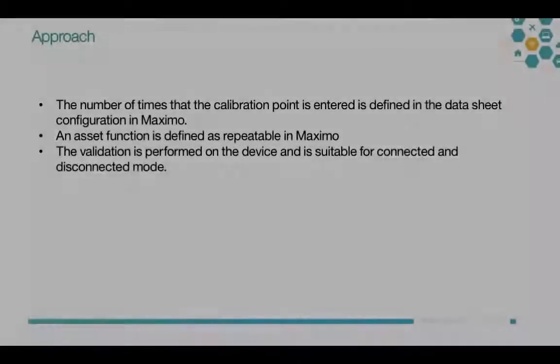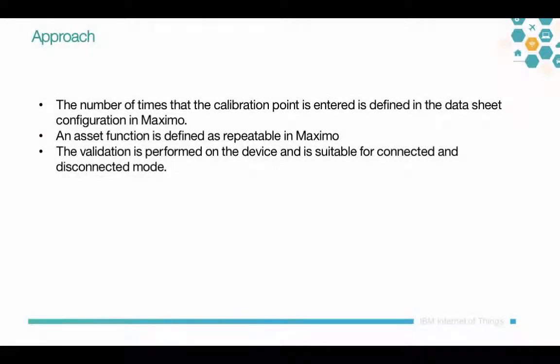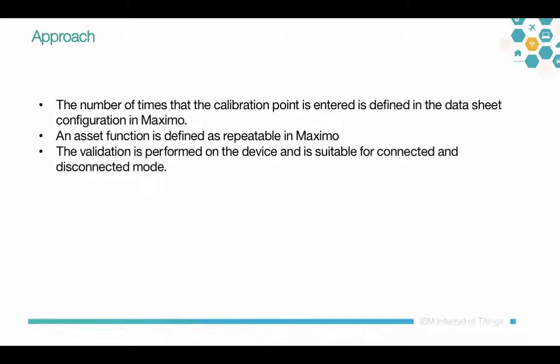A couple of things to be aware of here: The number of times that the calibration point is entered or repeated is defined in the datasheet configuration in Maximo. The asset function needs to be defined as a repeatable in Maximo. And finally, the validation is performed on the device itself, so it's suitable for both connected and disconnected mode.